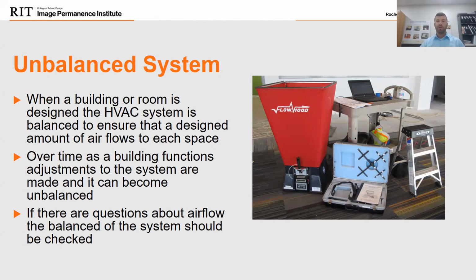It's almost like managing water flow. If you want a certain amount of water flowing out of this spigot and you're running it out of several others at the same time, then you have to adjust all the different spigots so that you get the right amount. It's similar with airflow. They're going to have to adjust different diffusers around a room to get the balancing right. And typically that little red hood shown in this image is what they'll use.